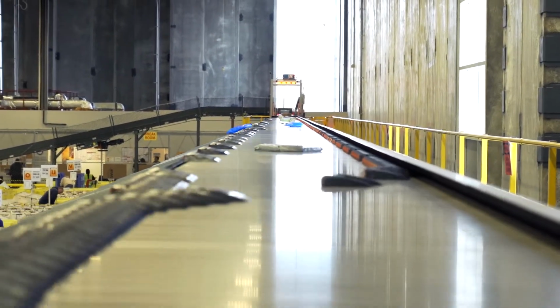Early on in our data gathering, we're seeing some exciting trends. We're seeing that when you rebuild a sorter, you see 4 times less factor of vibration. You're seeing 7 amps less amp draw from that sorter. Those are all things that are going to bring quick ROI to a connected solution.